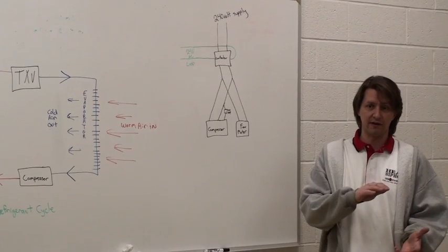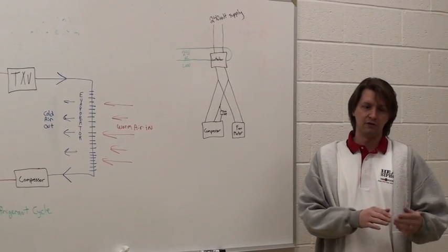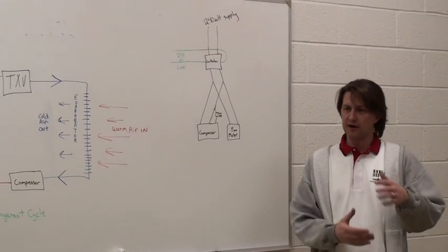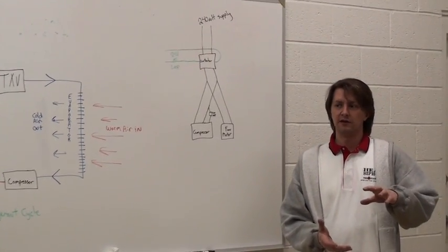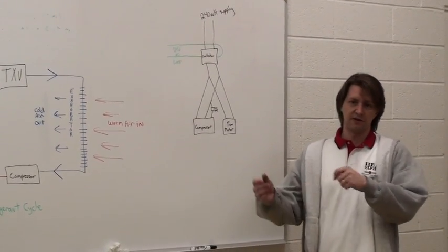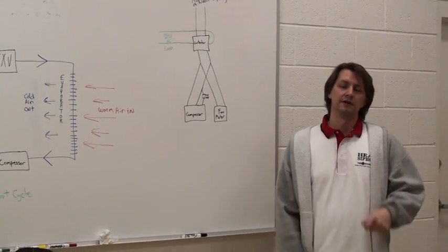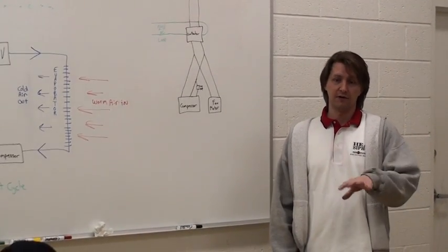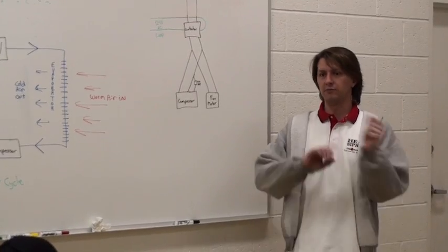You can't top it off. Like if you're low on R22, you can't just top it off with 422B. But if you're having troubles with that unit and you don't want to switch pressure switches and do a washout and change to like 407C, this one is a drop-in where you just pull out, put in.